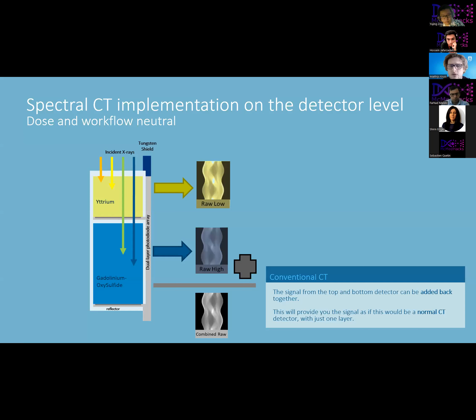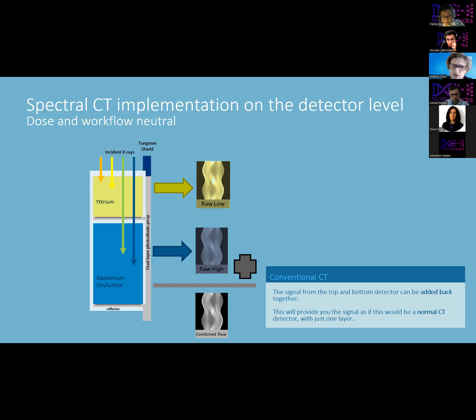And another nice thing about this is that by integrating the energy from the low and the high detector, you can recombine this and basically reduce this system back to a single layer detector. So a detector that you normally have around, and this is what we call the conventional CT, and this is by all means the same scan as what you would acquire with a normal scanner. So that's very nice for adoption, such that we can give that to the doctors as a sort of fallback, and also a starting point for their adoption.